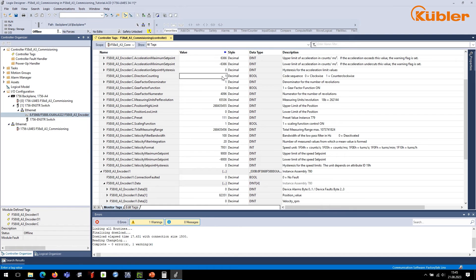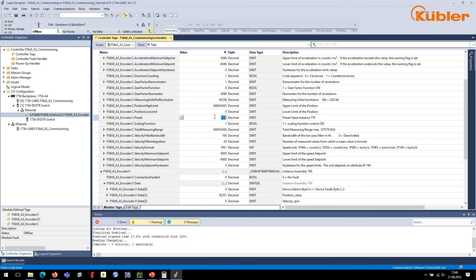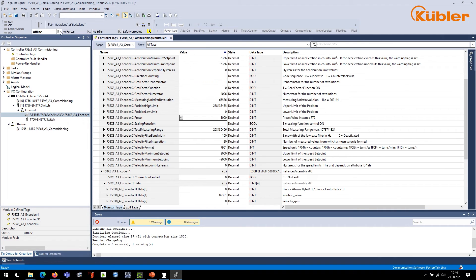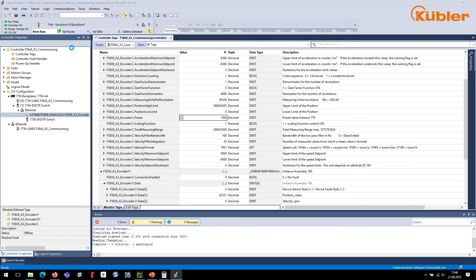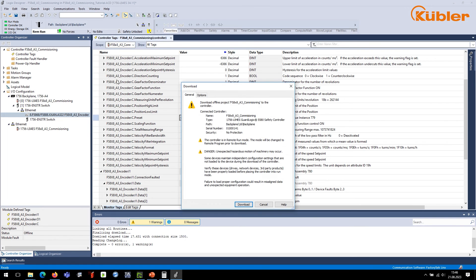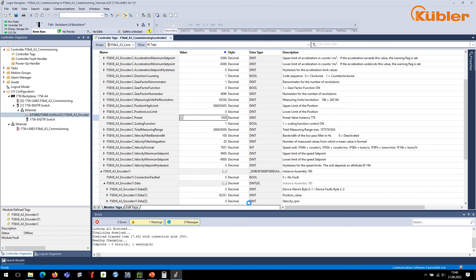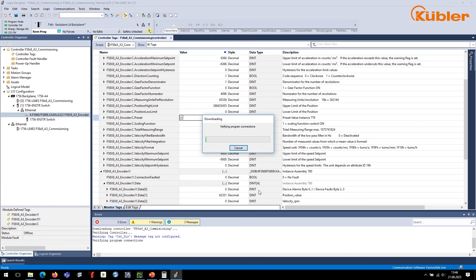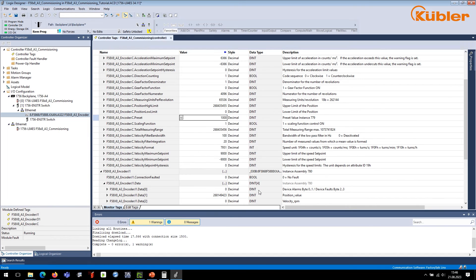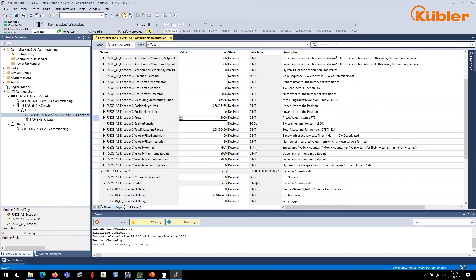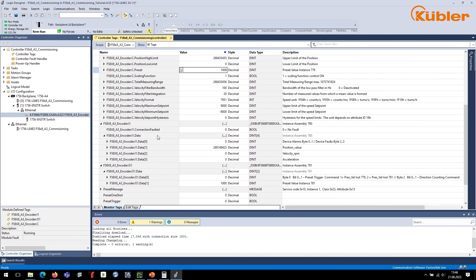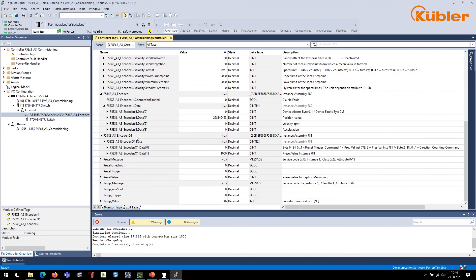For a preset, it is important to understand that only the preset value can be set in the configuration assembly. The trigger has to be set in the output data of the encoder. To configure the preset value, go to parameter preset and assign your preferred value. In this example, we set the value to 1000. Triggering the preset is done through the output data. To watch the effect of the new configuration, go offline and go online again. By turning the shaft counterclockwise, the position values increase.